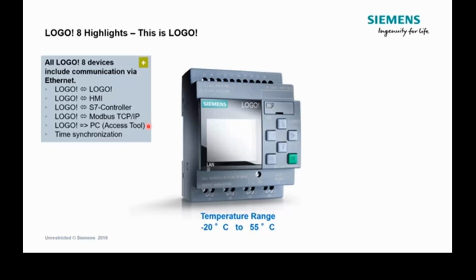Now, we've got data logging capabilities in the Logo, so they're typically executed from the user program, but that has a slight downside to it in that when you want to retrieve the log files, you've got to use the Logo Soft Comfort software and you've got to put the Logo into stop. So at that point, you would lose control of your machine.